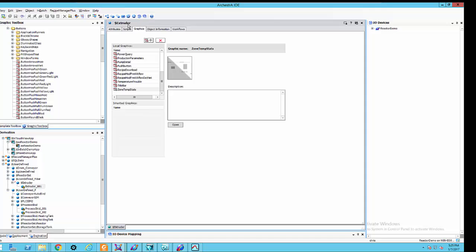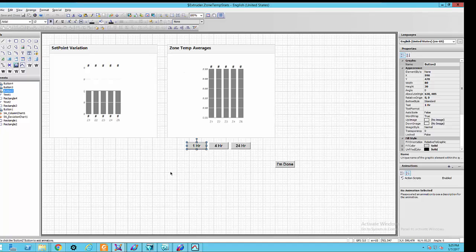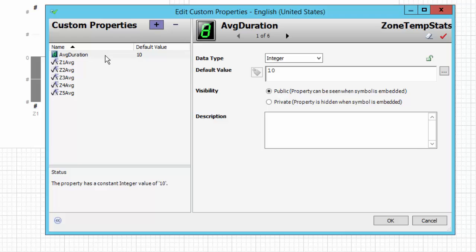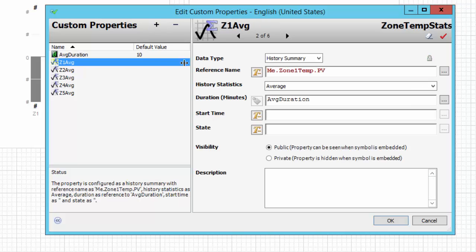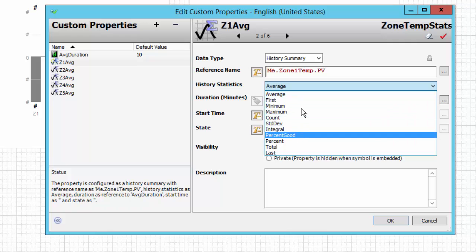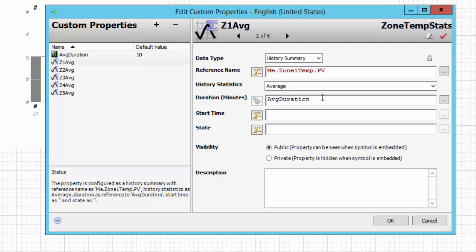We also have a graphic called Zone Temperature Stats. When we open that graphic and look at its custom properties, we have a few defined. The average duration property drives what duration the system should query in the past — whether that's the past hour, past four hours, or past 24 hours. We also have Z1 through Z5 average, with the data type set to History Summary, which gives access to statistics from the Wonderware Historian such as minimum, maximum, and average. We choose average here, and for the duration we bind it to the value of our average duration custom property.